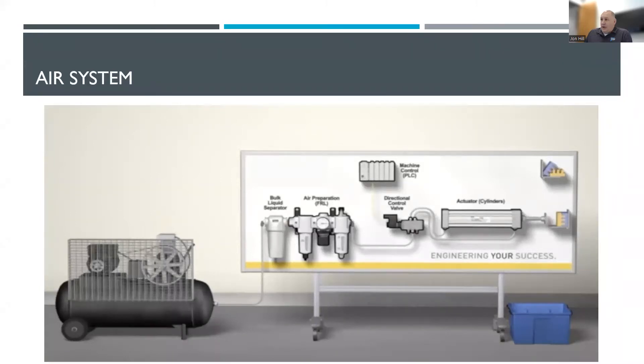There are also particulates, dust, and quite a bit of oils in the air. So we run it through a liquid separator and then through filtration items. We also have a pressure regulator — we might have a 200 PSI tank, but our actual working PSI might be around 80 to 90 for a lot of applications, so we run that through a regulator that only lets that much pressure through into the working part of the line. Pretty much every system is going to have some sort of air preparation, probably at multiple locations. You might also have a cooler, since compressing air tends to create heat.